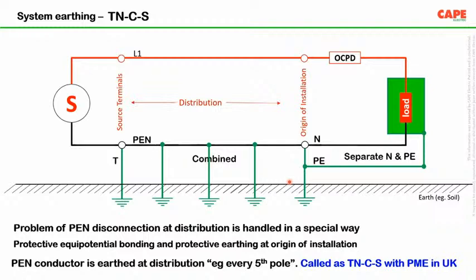Exactly. That means we are having a redundant earth. Suppose in case of any disconnection, that particular redundant earth can take care of it, and also the equipotential bonding as it is being taken at the working area. So the quantum of current also will not flow in case of an accidental connection of a metal body to the live conductor. Another question, let me go very quickly to this one.